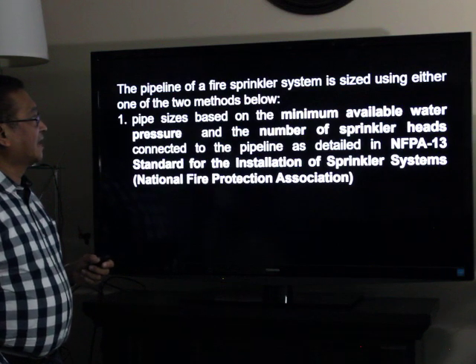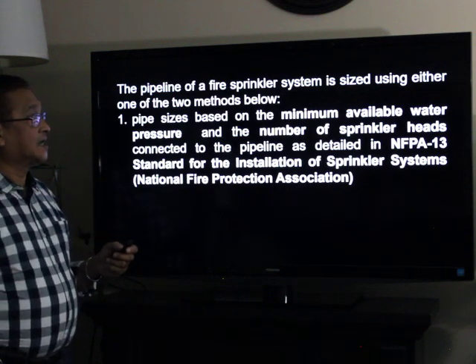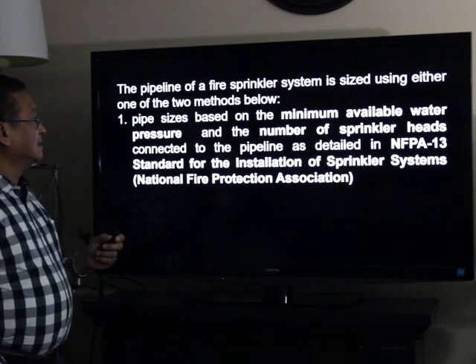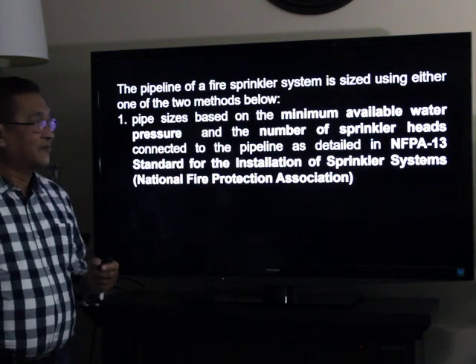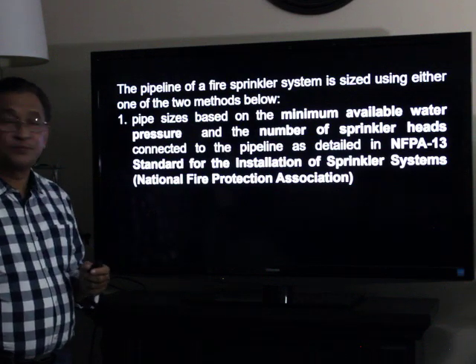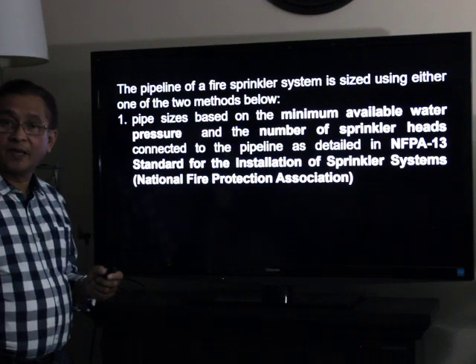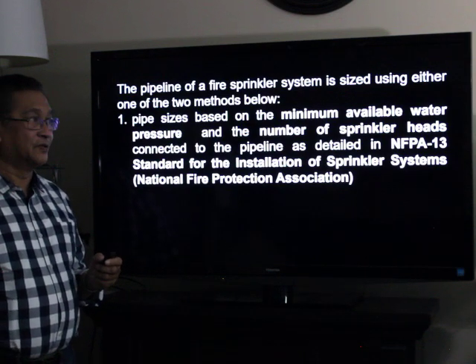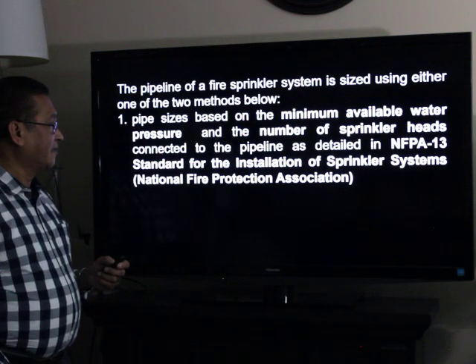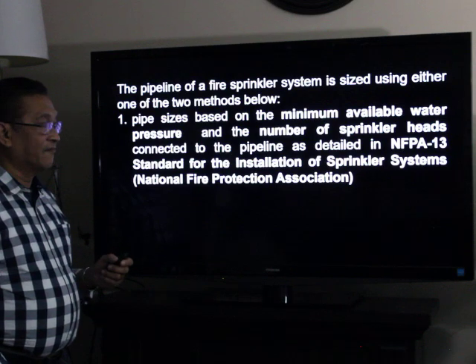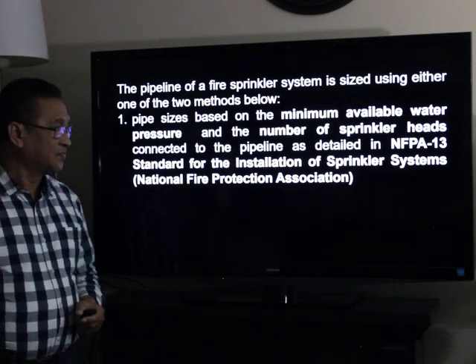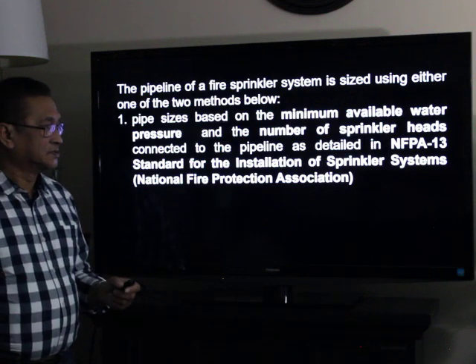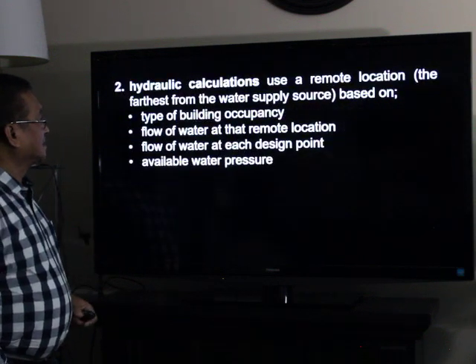The pipeline of a fire sprinkler system is sized using two methods. The first one is based on the minimum available water pressure and the number of sprinkler heads connected to the pipeline, as detailed in NFPA 13 — the National Fire Protection Association standard for the installation of sprinkler systems.